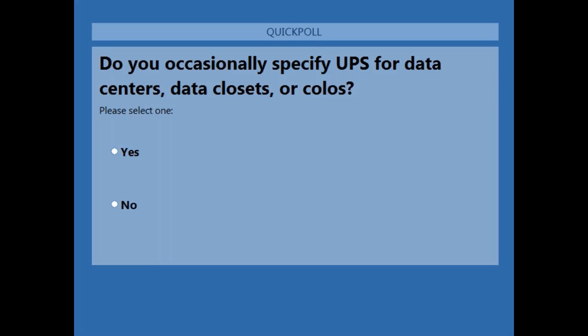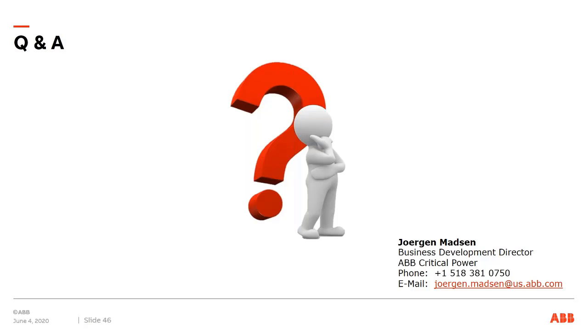But without that, it's a little tricky to make sure that you have redundancy in a distributed redundancy system. Right, because your UPS doesn't tell you that, hey, I'm 80% full of load. Well, it can. The UPS can tell you how much is loaded. You can get that with Modbus or whatever monitoring is used.